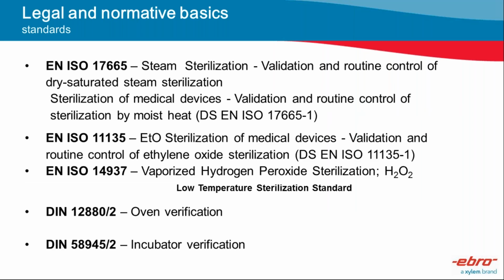So to summarize, the pharmaceutical and medical are founded and they are guided by different and specific norms. For steam sterilization, we have the EN ISO 17665. For ethylene oxide sterilization, we have the ISO 11135. And for the hydrogen peroxide sterilization, this is quite new, which is the ISO 14937. And in pharmaceutical, they are also guided by norms with oven verification and incubator verification because these processes are also very critical in the pharmaceutical processing industry.